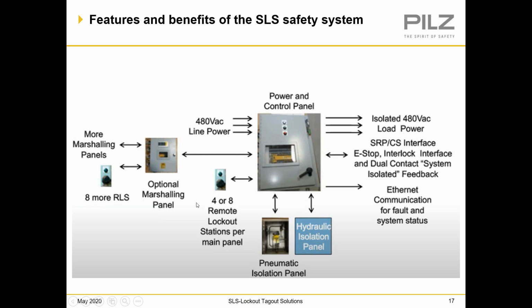As a matter of fact, we have an application at a diaper manufacturer that had a few issues, and they ended up, on average, using 24 of these remote lockout stations in a typical cell. And they had 2 issues. The first one is the obvious one, where they were doing a lot of lockout using disconnects, and they were replacing disconnects all the time as a result because of the frequency of lockout. And they had a lot of entry points within the machines, and they would prefer ways of disconnecting or locking out at each entry point. And so the SLS proved to be an excellent solution for them. And so that's why they went from the old approach to the SLS solution.